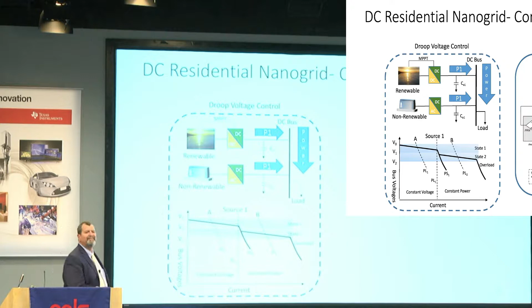DC has a huge advantage because there is nothing simpler than controlling power in DC, because power in DC is voltage times current. If you want to regulate the power that you are getting from here to here, you use what is called droop control. You put the power that you want to get the most to a higher voltage level, and then you use that voltage level. When you begin to demand more power, the voltage will drop to a point you consider state 2, and at that moment, the generator that you don't want to produce power, but need now because your voltage is collapsing, will hold the power enough for a long time. As you see, droop control in voltage is extremely simple.